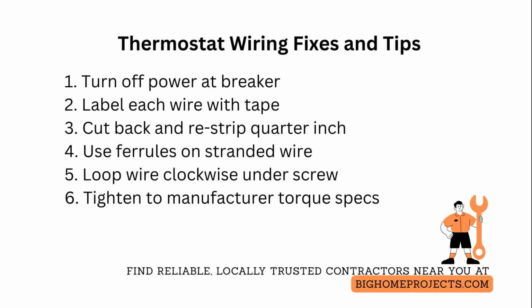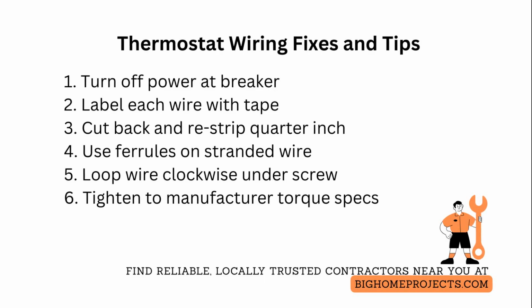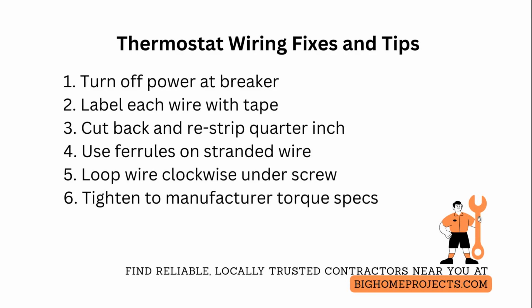Inspect each conductor end. If strands are frayed or nicked, cut back a 1/4 inch and re-strip straight so you have a clean, solid end. Or better, use a ferrule on stranded wire to prevent stray strands from shorting.